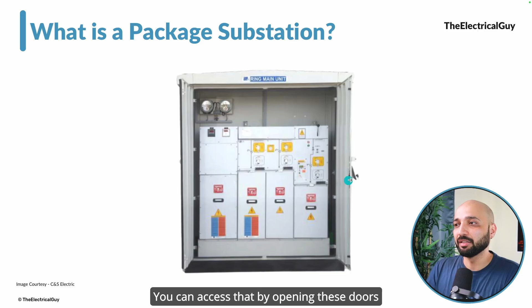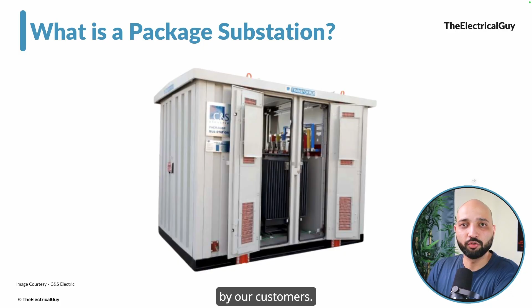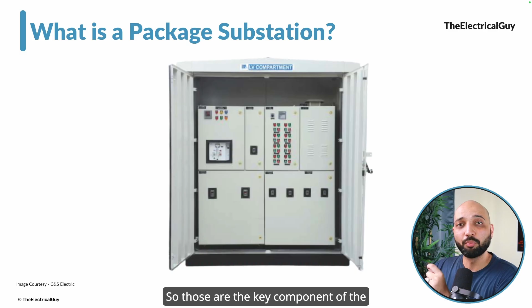Then you can see the transformer section in between, which can be opened using these doors. You can see the bus bars here, and the main transformer, which steps it down to the value usable by our customers. Lastly, we also have the LV compartment, with different compartments, ACBs, and indications for supply and on-off status. So those are the key components of the package substation.